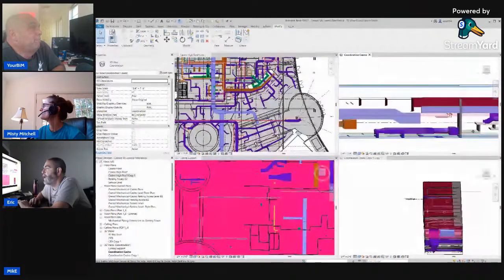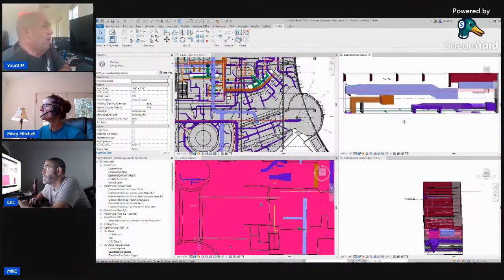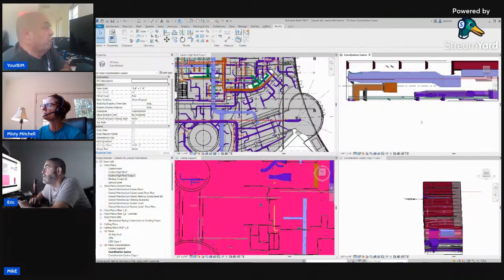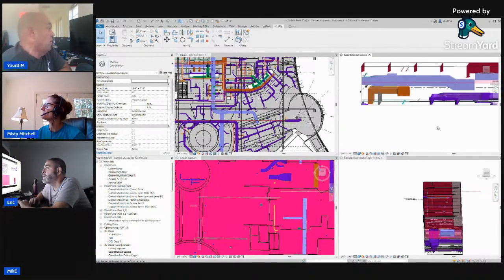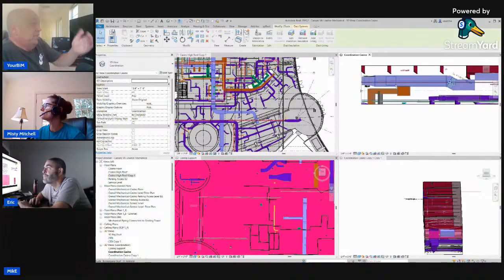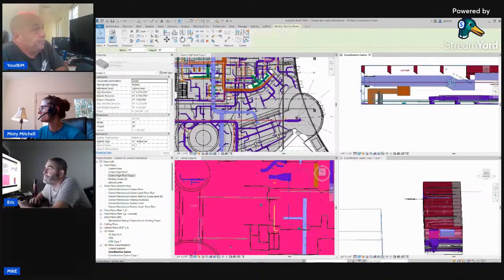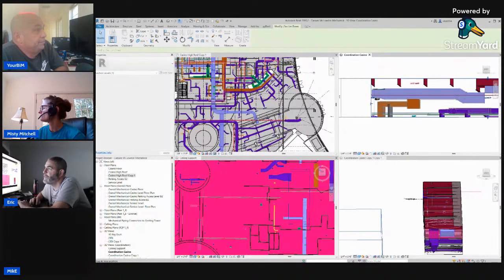Then do I want to do a 90-degree drop down and stay down there? I don't think I'd do a 90. Remember, you want to keep that flow going good. I'd try to do one of those 30s or 22 and a half, sort of like what they had right there. But the difference is now you're going to lower all that. And then I know you got to go back to the brown and you're going to have to put the brown above. Which is what this whole task has been doing.